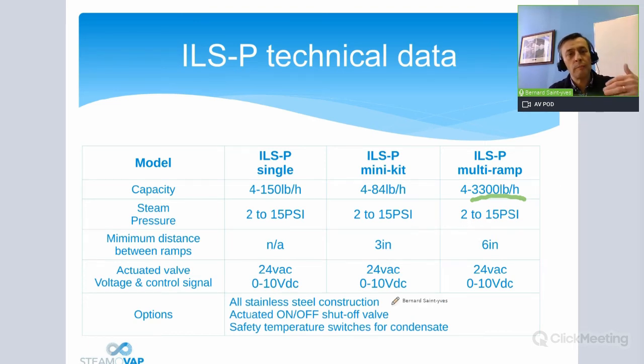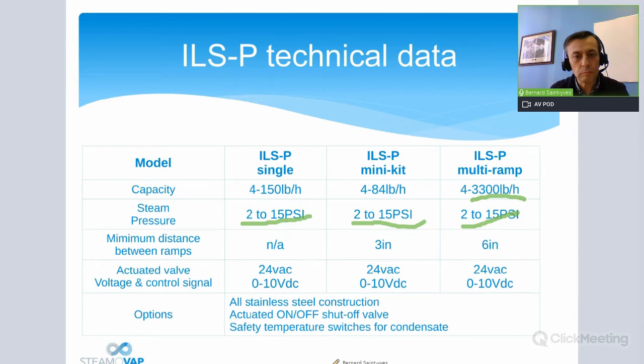Of course, the higher the capacity, the more ramps you will need, and the more steam traps you will need. There is also a limitation on the length of the preheat jacket that you can handle per steam trap. Okay, the steam pressure: all of the humidifier manufacturers will publish a 15 psi maximum.